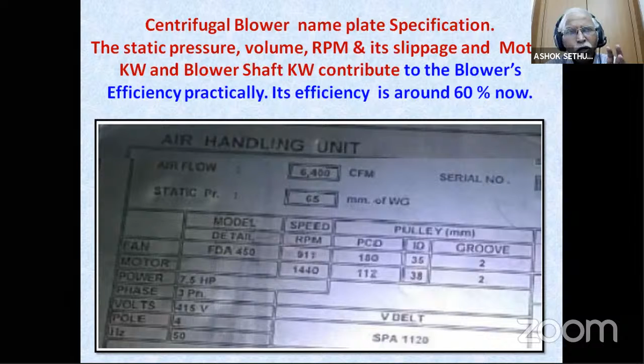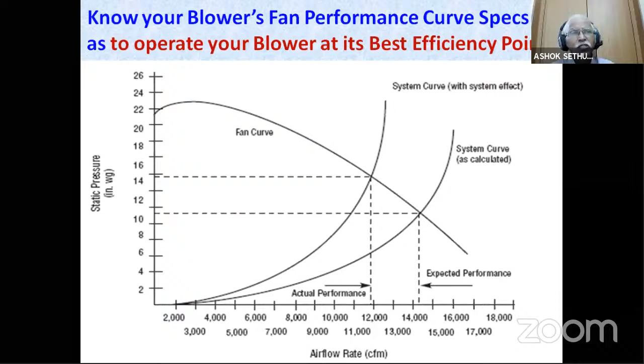If the blower is giving us some steady output, and if the output is getting choked due to some filters, automatically you can see the curve on the given blower. A blower with the highest flow with less static, if the static pressure is altered due to the system design by the duct design, automatically the blower gets derated. From 14,000 it came to 12,000, because the static pressure got altered.